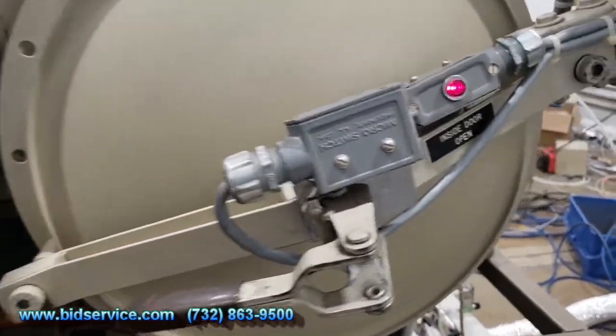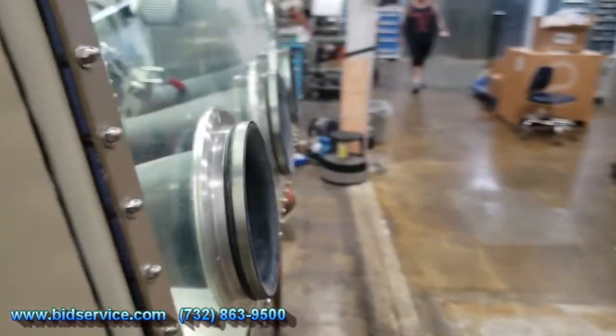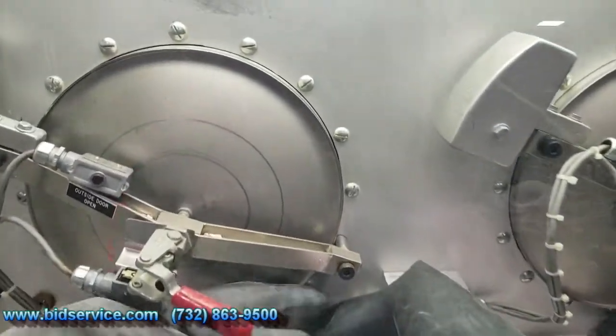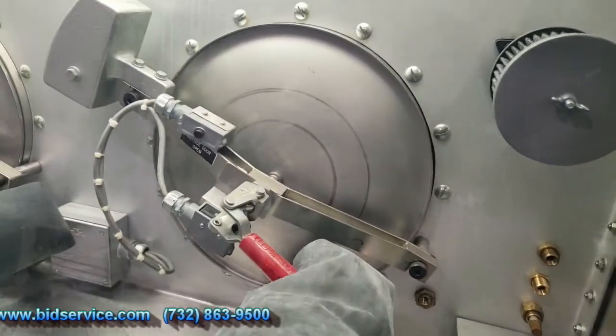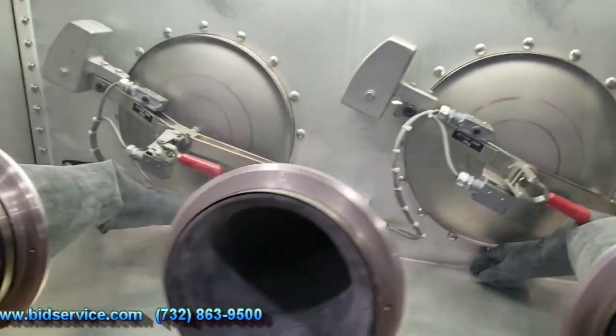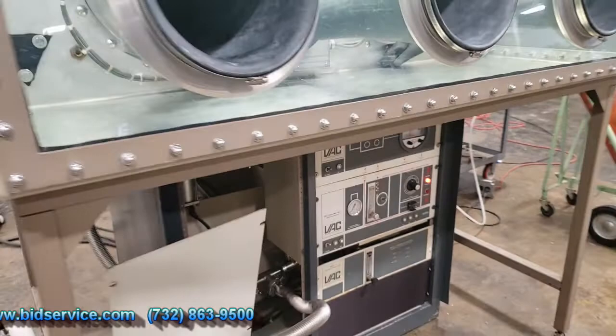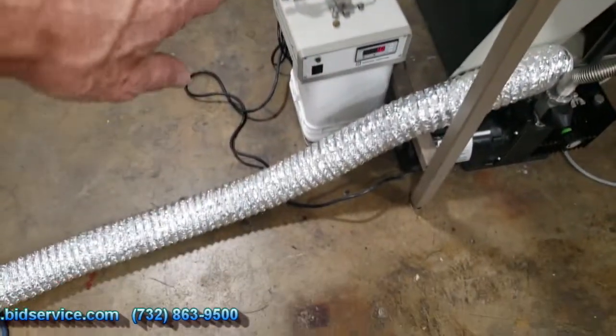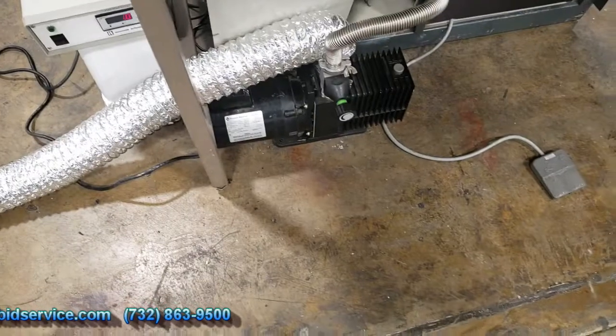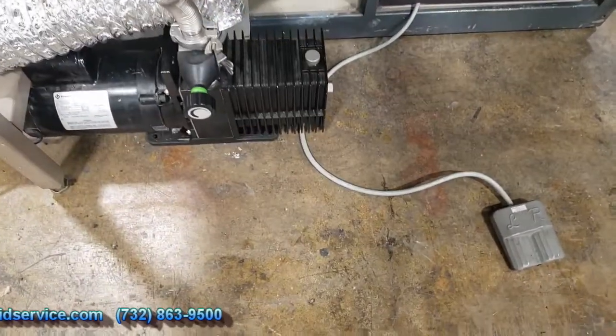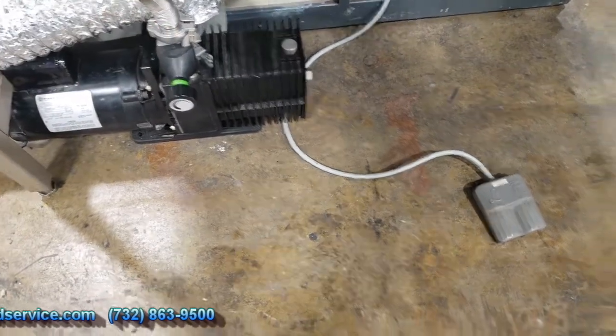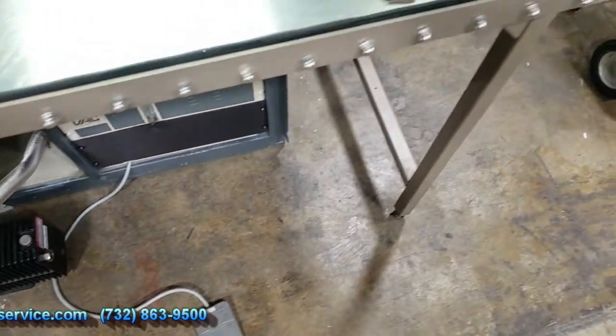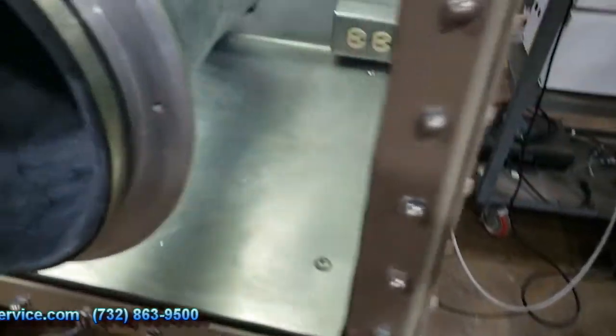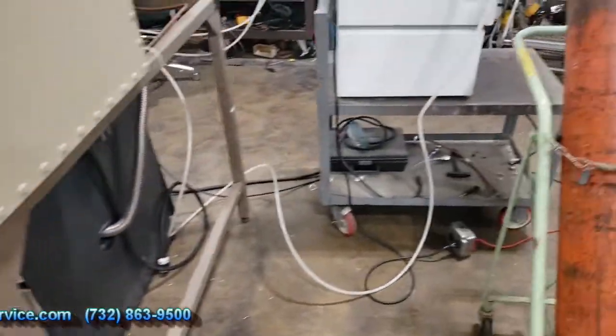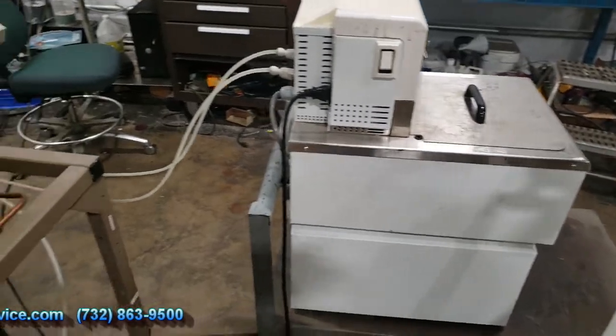Let's close these down. See that the indicators went out, and the same here. So again, the moisture monitor is not included. The vacuum pump is not included. You can use one vacuum pump for the dry train, maybe something a little bit smaller, and use one for each of the antechambers if you'd like. For demonstration purposes, I just hooked them all up to one. The regulator and cylinder you need to provide, and chilled water from a chiller you'll need to provide.